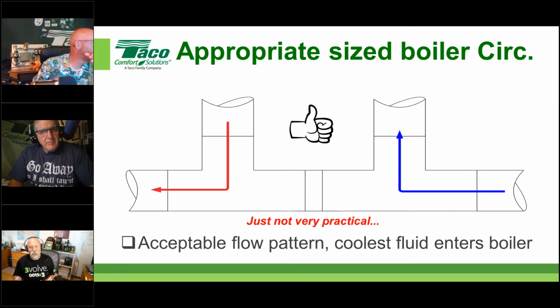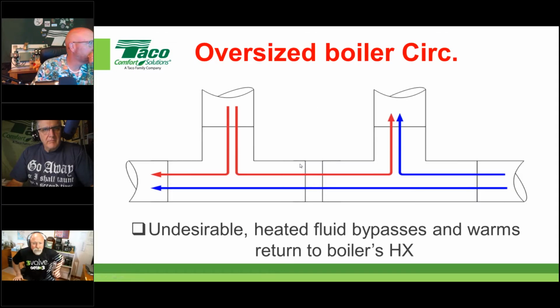So anyway, just pipe it without primary or secondary if the boiler manufacturer will allow it. Here's where we get into trouble - when you oversize your boiler circulator, you're going to get this, and I'll make an upfront statement: you're going to get a little bit of this anyway, especially on those shoulder conditions.